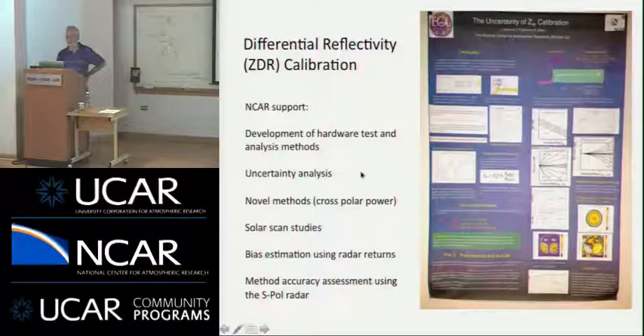On that topic, basically we had funded NCAR to do a lot of investigations using S-Pol, including supplying some hardware for automatic test equipment sort of things. And if I recall correctly, at the time, the general conclusion was that with on-equipment hardware type test measurements, your uncertainty overall would probably be not much better than about 1/4 of a dB. And it's just because these uncertainties from all the different hardware measurements add up as you go along. And I believe that's been proven out in our experience with the production system. So that has led us to looking at external targets as a way of assessing the performance of the radar, and I'll get to that in a minute.